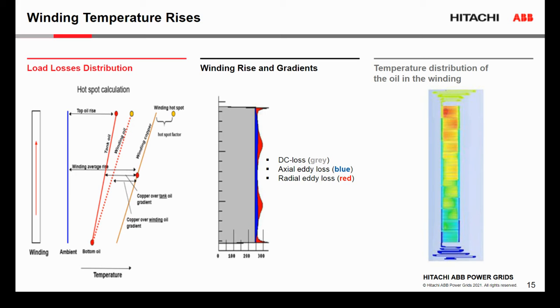Those losses are driven mainly by the radial eddy losses due to the radial component of the flux. And with higher temperature on the top of the winding, and also with the much higher losses in the first few turns or first few discs, we see that the hotspot is always located somewhere on the top of the winding. It's either the first or second turn or disc from the top.